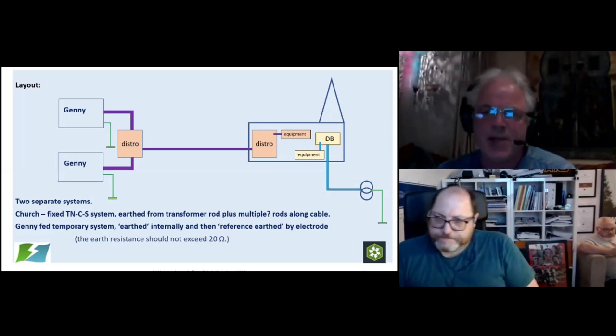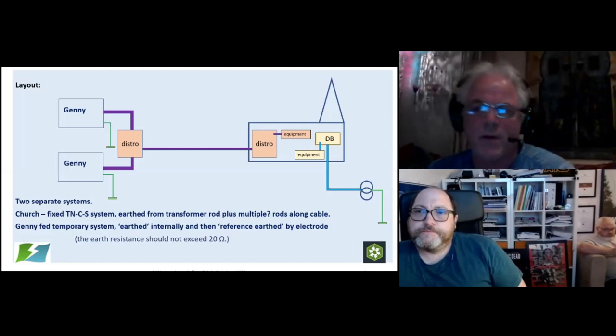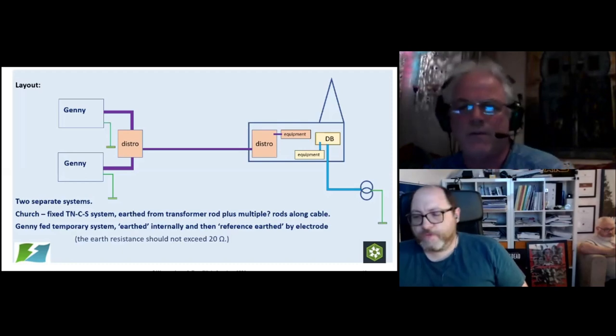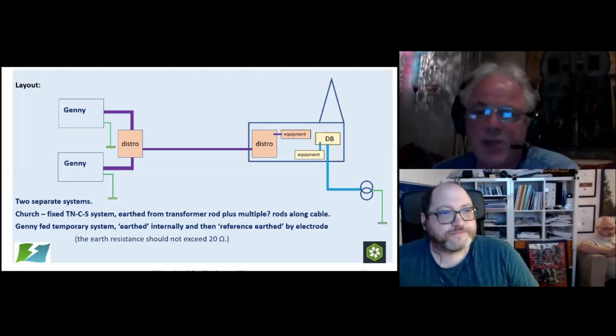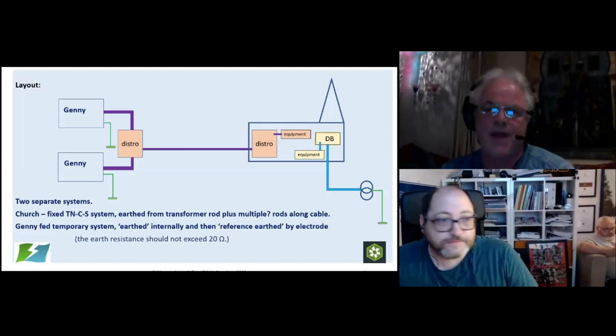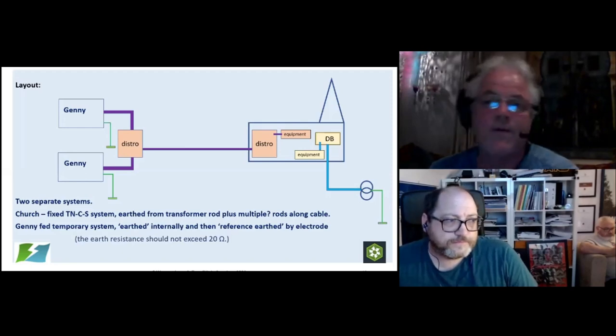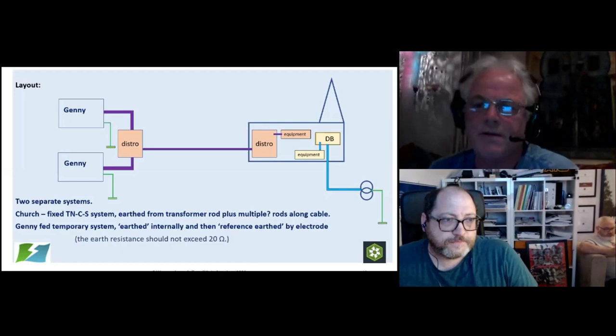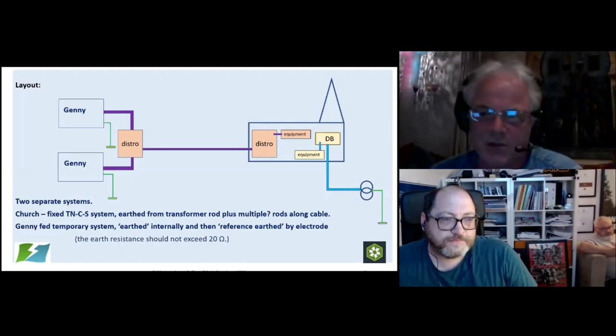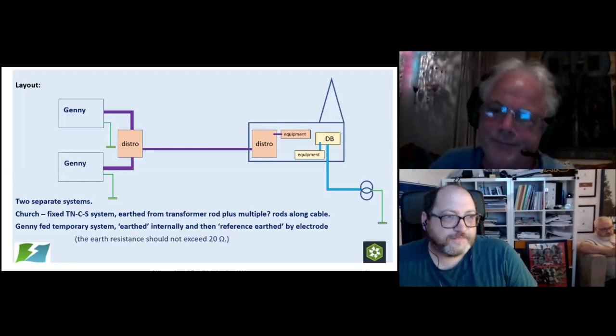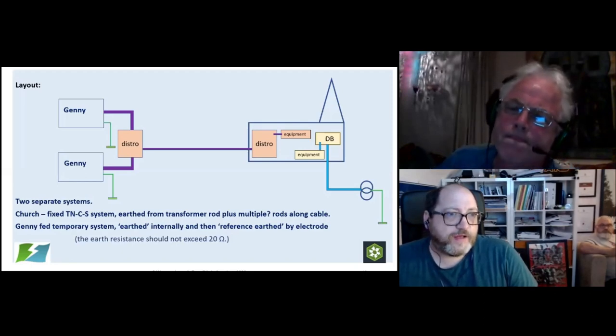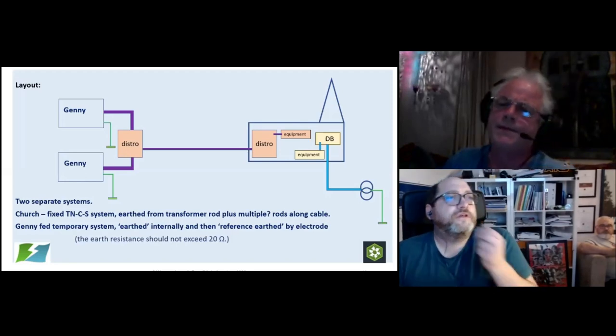In between events, they will be checked suitably for the type of equipment. So whatever tests are suitable for that type of equipment will be done. If it's specialist equipment like dimmer racks and stuff like that, then that will be tested. Hopefully, it'll be tested by a specialist firm and not given to any old bod doing a PAT test, whacking 500 volts through it, because I don't think it'll do it a lot of good. Okie dokie, great. Okay, Sean has asked.